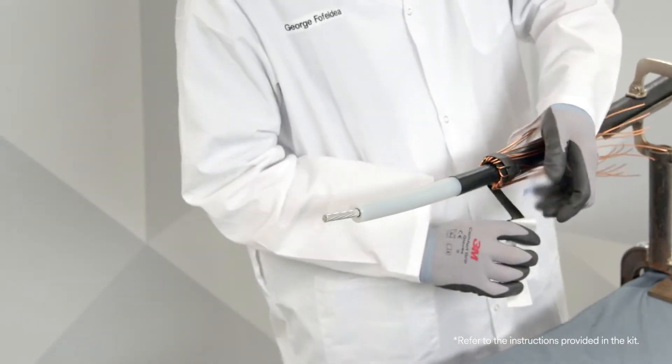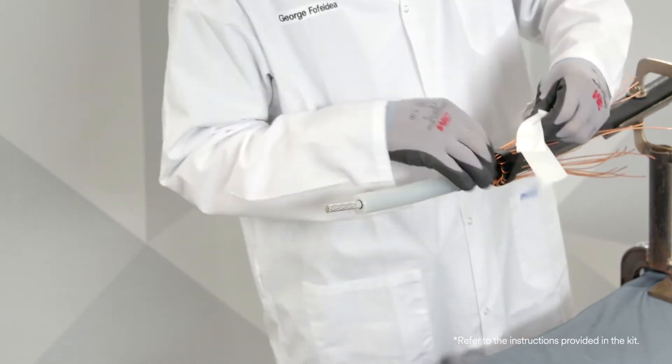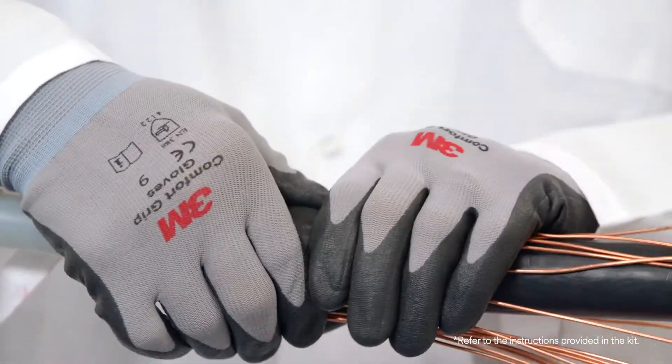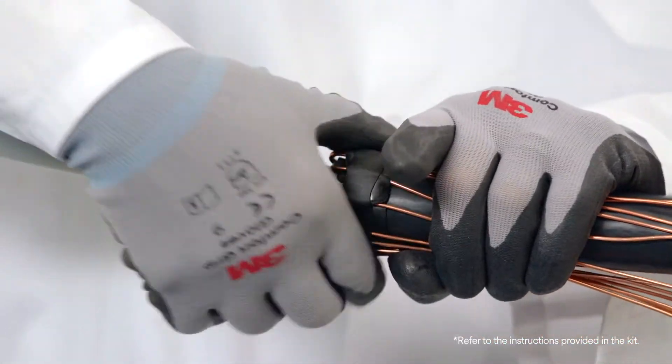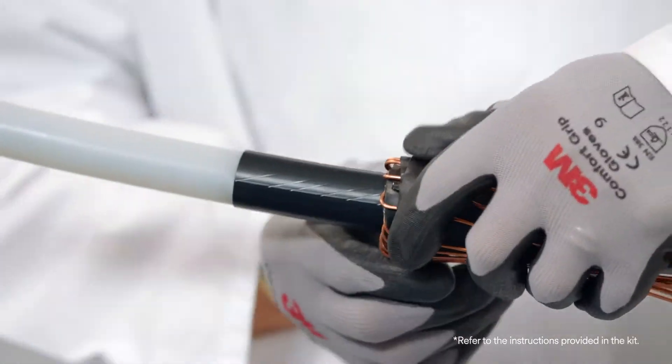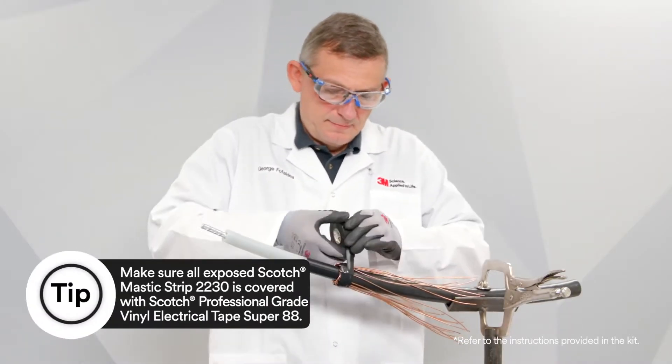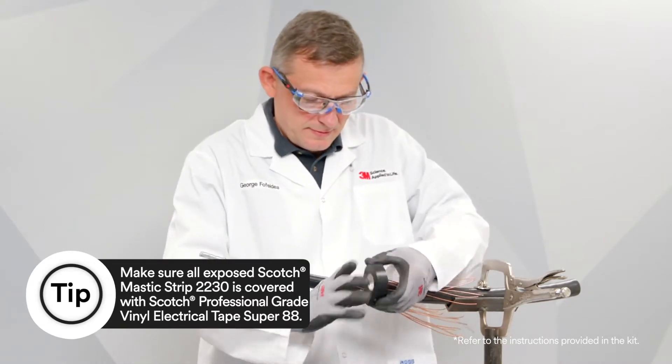Now apply a single wrap of the Scotch Mastic Strip 2230 over the neutral wires and then compress neutral wires into Scotch Mastic Strip 2230 by overwrapping seal strips with two highly stretched layers of Scotch Professional Grade Vinyl Electrical Tape Super 88.